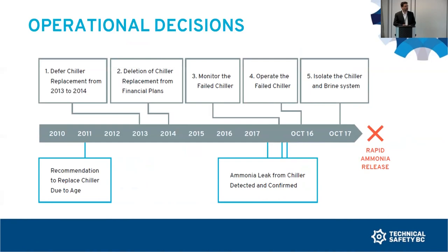A failure of the chiller was detected during the shutdown period in the spring of 2017, so ammonia was found within the brine system. Through discussions between the maintenance contractor and the operator, a decision was made to monitor the failed chiller, which, the day before the incident occurred, led to a decision to operate the chiller. It was shut down at that period, following the event the night before, where there was leaking through the brine expansion tank, which led to the isolation of the chiller and brine system through closing of those valves.